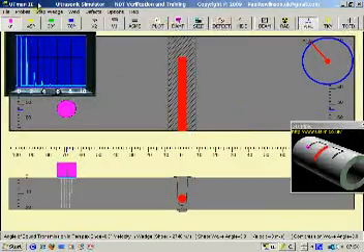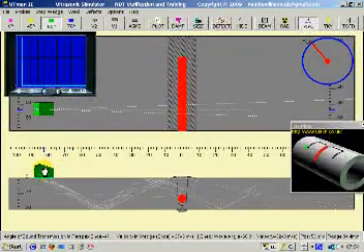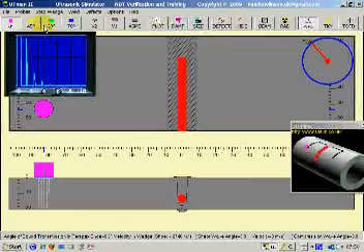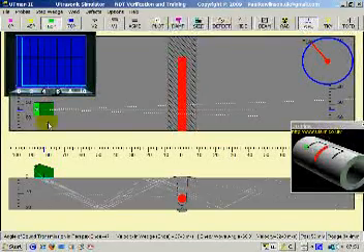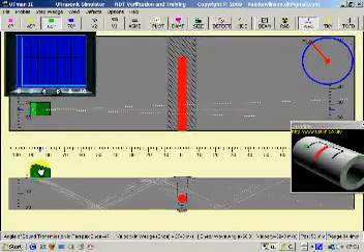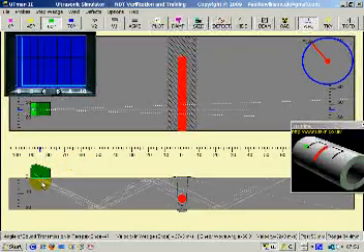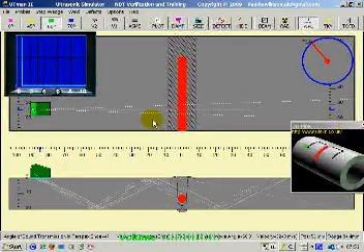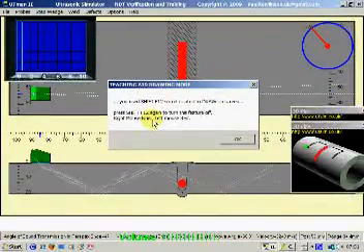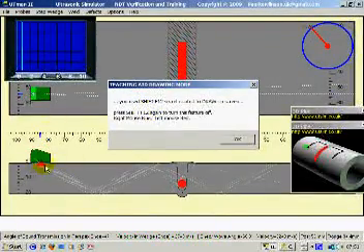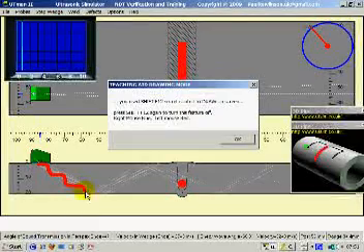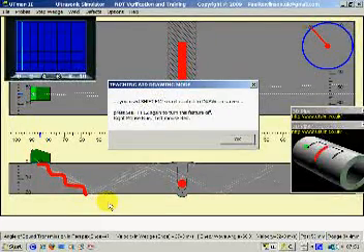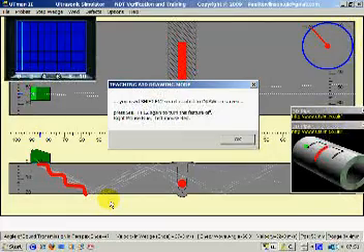Now, the angle probe, that is called shear wave. The zero is called compression wave. These angle probes are transmitting in shear wave. And here, the wave is more of a wave and, in fact, travels more like that. And it is approximately 3,000 metres per second in carbon steel.